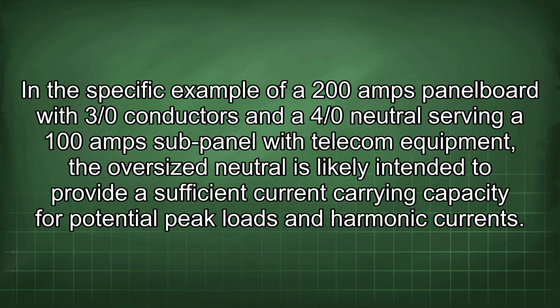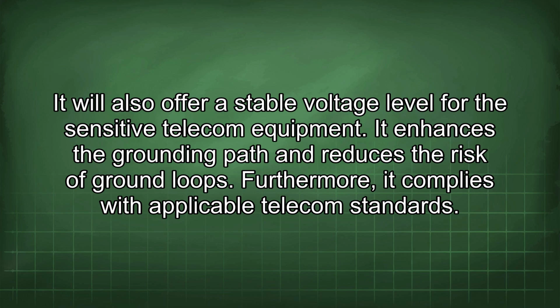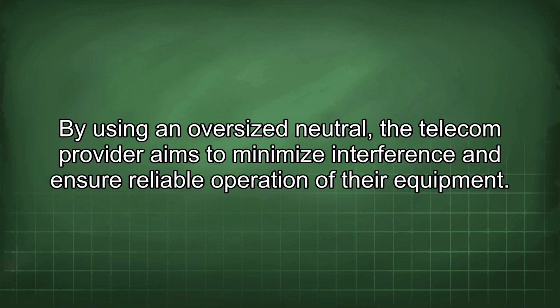In the specific example of a 200 amps panel board with 3/0 conductors and a 4/0 neutral serving a 100 amps sub-panel with telecom equipment, the oversized neutral is likely intended to provide sufficient current carrying capacity for potential peak loads and harmonic currents. It will also offer a stable voltage level for the sensitive telecom equipment. It enhances the grounding path and reduces the risk of ground loops. Furthermore, it complies with applicable telecom standards. By using an oversized neutral, the telecom provider aims to minimize interference and ensure reliable operation of their equipment.